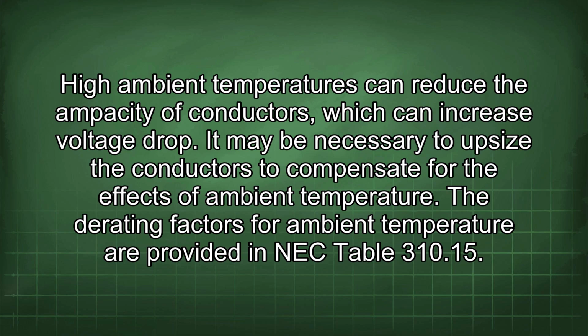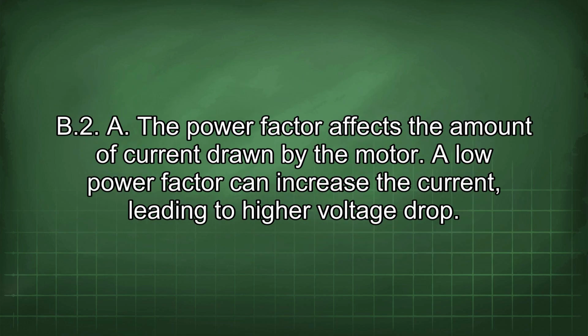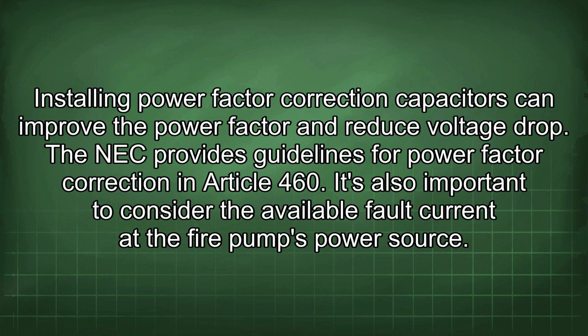The derating factors for ambient temperature are provided in NEC Table 310.15(B)(2)(a). The power factor affects the amount of current drawn by the motor. A low power factor can increase the current, leading to higher voltage drop. Installing power factor correction capacitors can improve the power factor and reduce voltage drop. The NEC provides guidelines for power factor correction in Article 460.